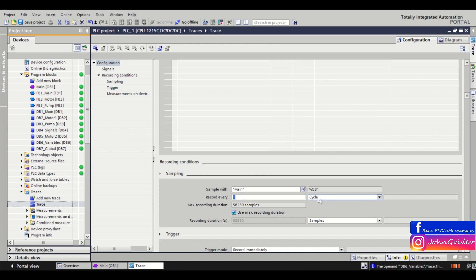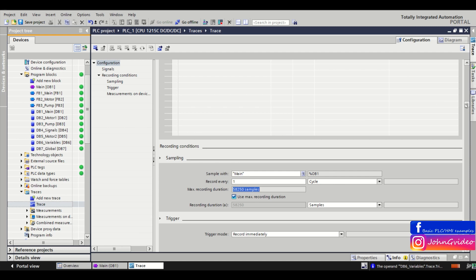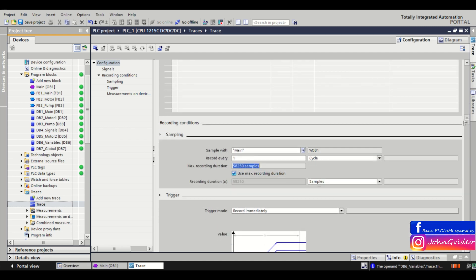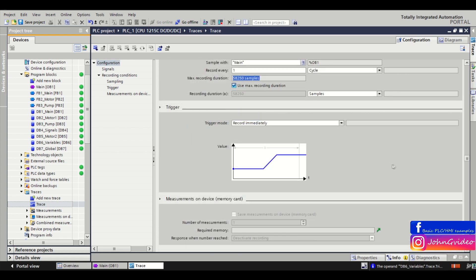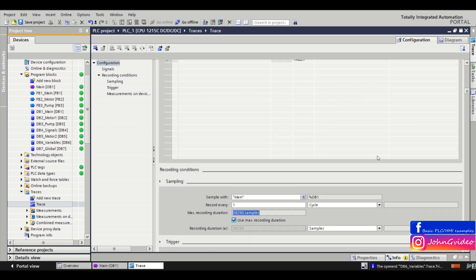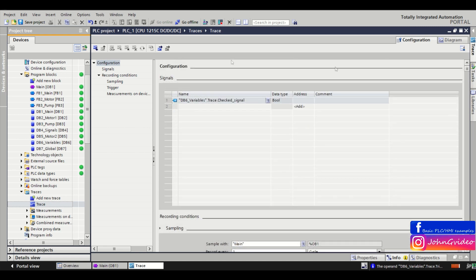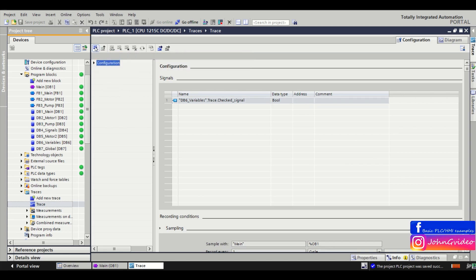Then we set we need to record every sample, every cycle of the PLC, using the max recording duration. For this situation it's 58,250 samples. We want to record our trace immediately. So save the project and now we transfer trace configuration to the PLC.